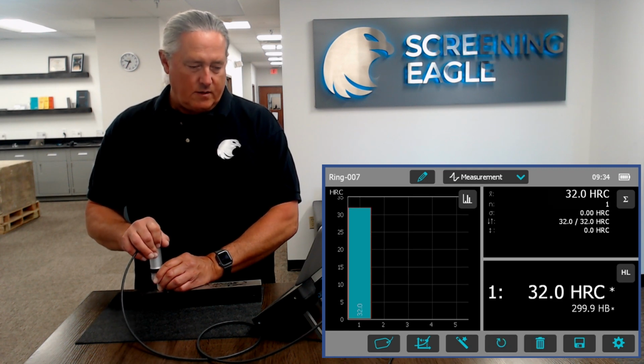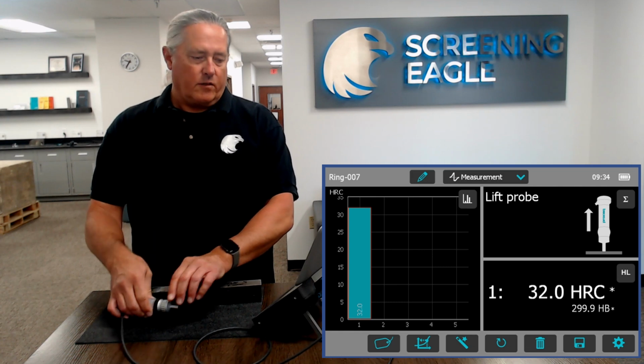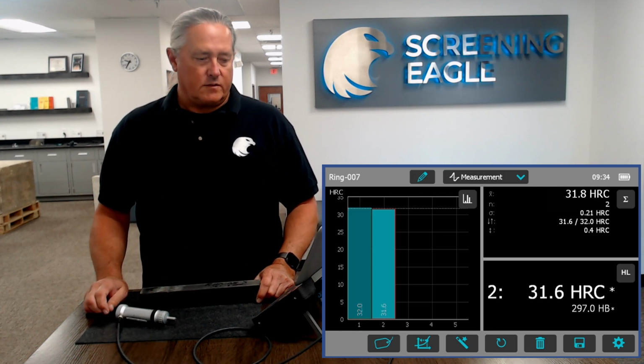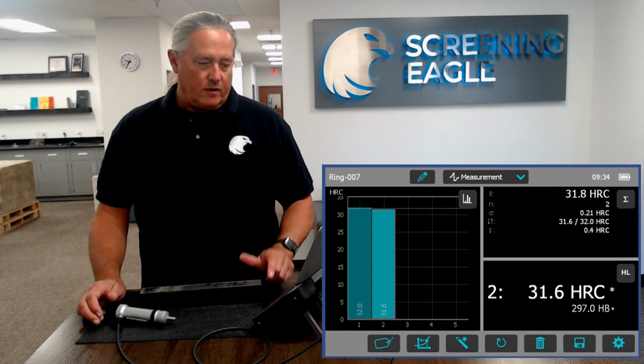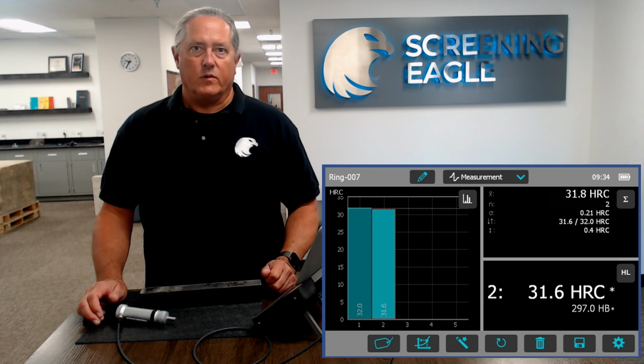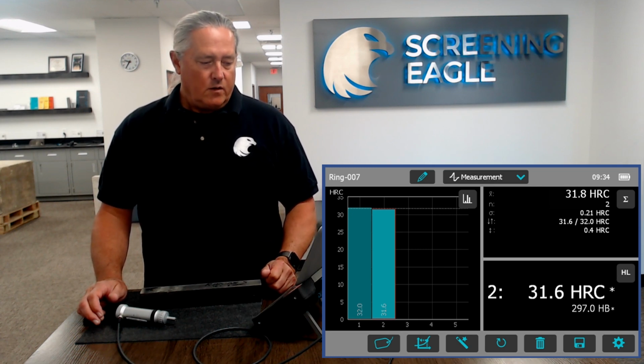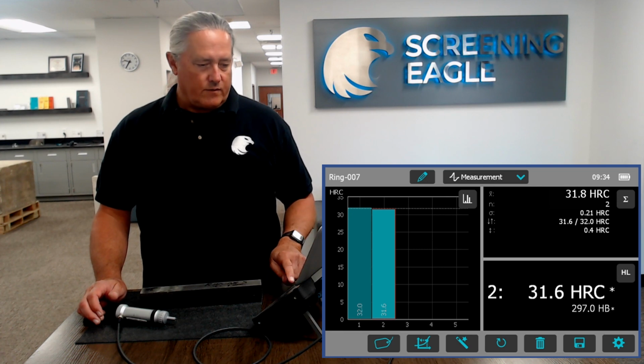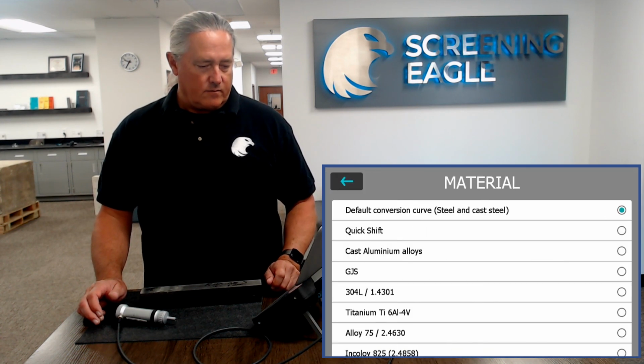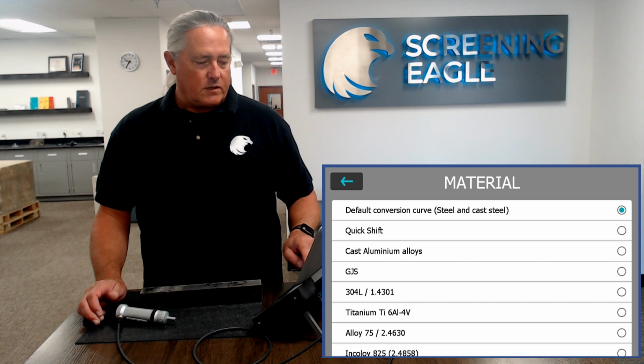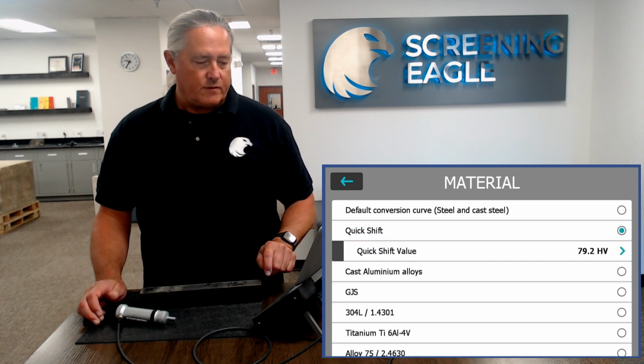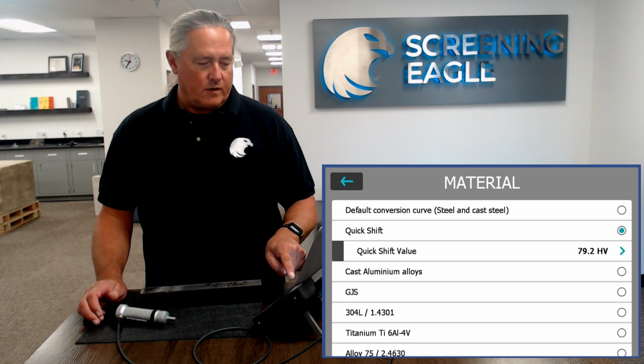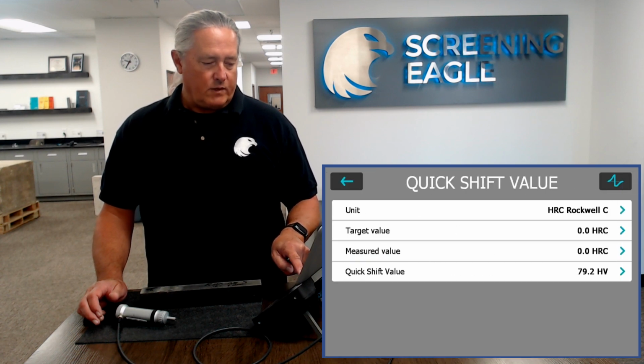So you can see we're getting into the low 30s for our readings. So I can either note right now my average is 31.8, and I can use that later, or I can just go into the quick shift and do things in a different way. To go into the quick shift, I tap on the material tab, and then I tap on quick shift, so the tick box is highlighted. And right now you can see there's a quick shift value already entered in, but we're going to overwrite that.